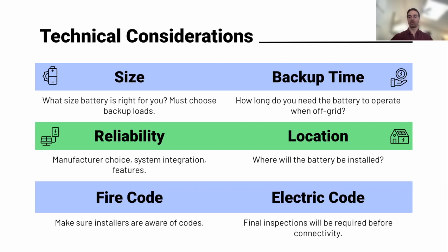When you get greater than a 20 kilowatt hour battery, some pretty significant changes need to happen to the room where that battery is installed, which can add cost to the project -- fire-rated sheetrock for the walls and other requirements. That's available on the state website, and I can certainly provide that resource -- the fire memorandum -- which is what we use to understand what's needed for the batteries.